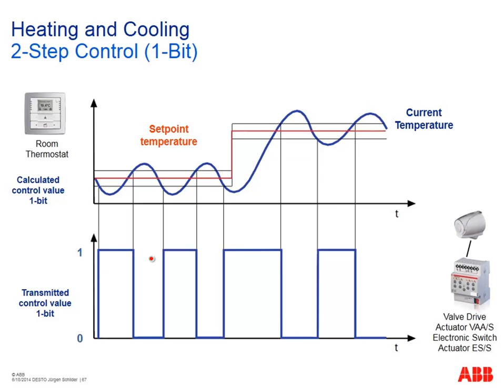Or you program directly the pulse width modulation, which is a bit different. What does it mean? The room thermostat calculates a control value, as always, as an 8-bit telegram. It's a value, for example, 10% or 20%. But it will be converted into an on-off telegram as well. We call it pulse width modulation because during a certain period, a cycle time, we open the valve for a certain time depending on the control value, and we close it.